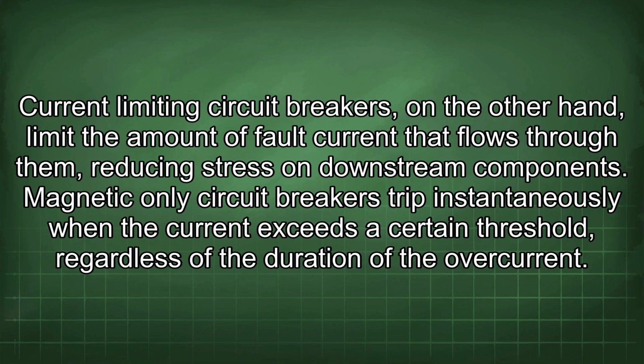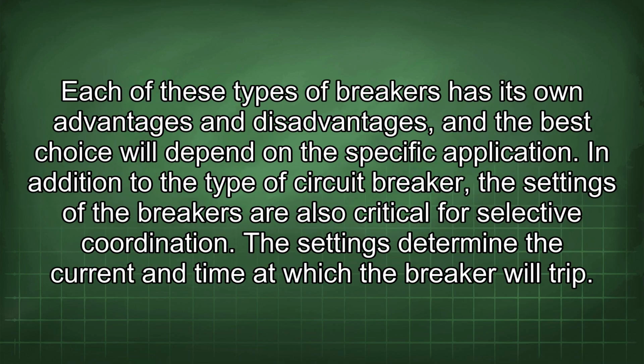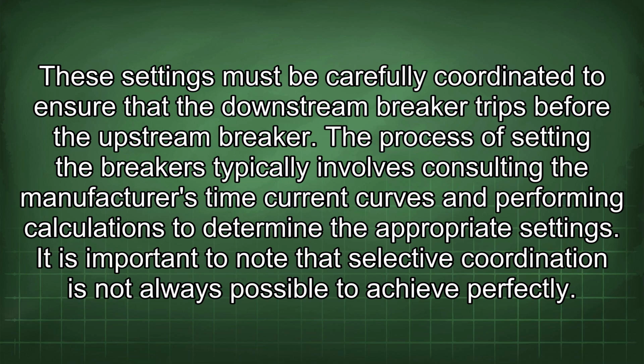Magnetic-only circuit breakers trip instantaneously when the current exceeds a certain threshold, regardless of the duration of the overcurrent. Each of these types of breakers has its own advantages and disadvantages, and the best choice will depend on the specific application. In addition to the type of circuit breaker, the settings of the breakers are also critical for selective coordination. The settings determine the current and time at which the breaker will trip.